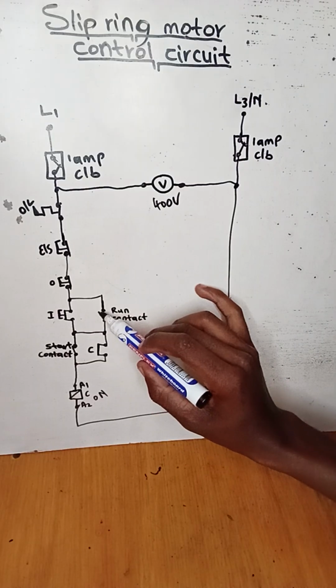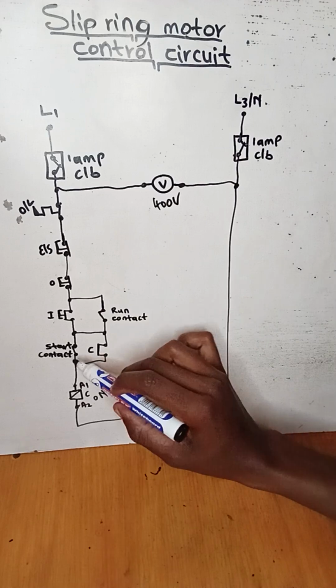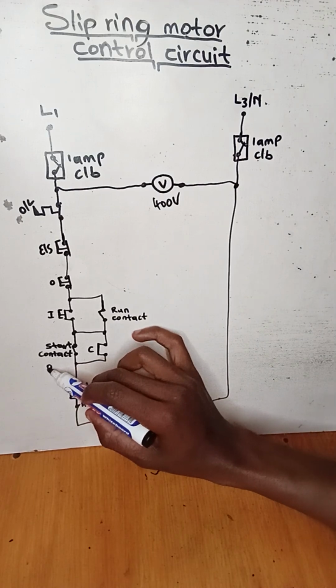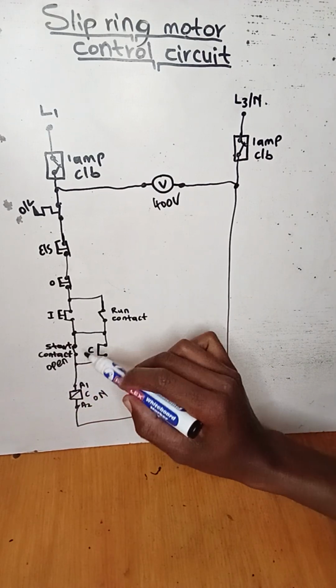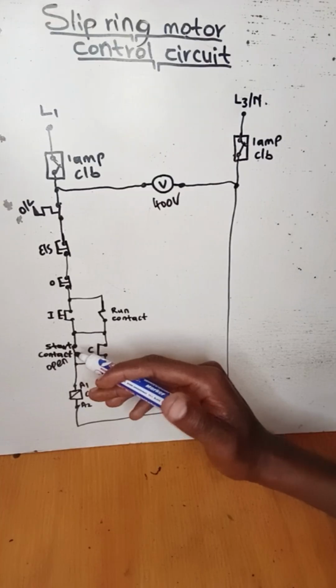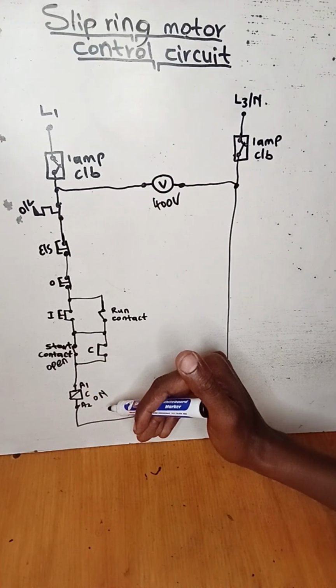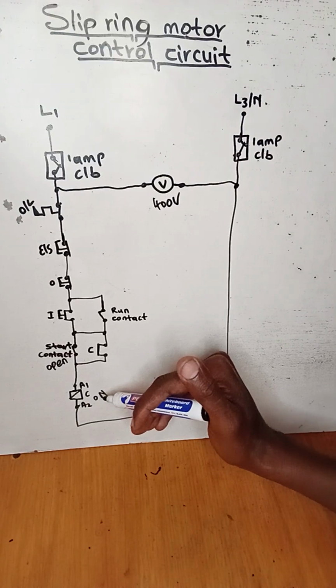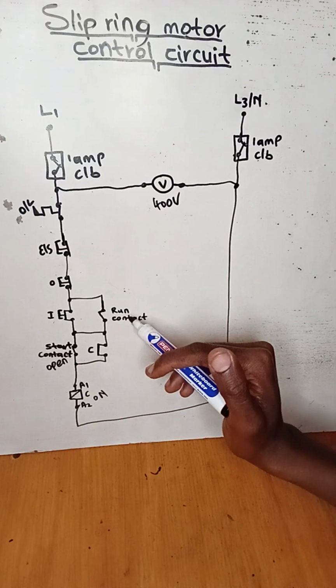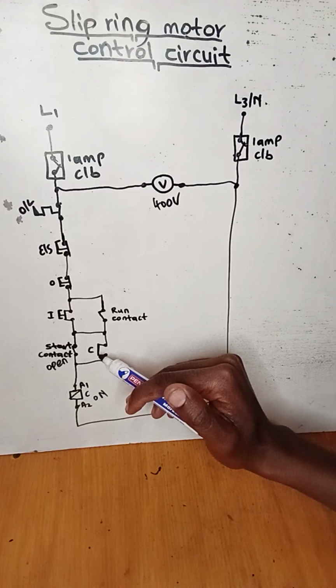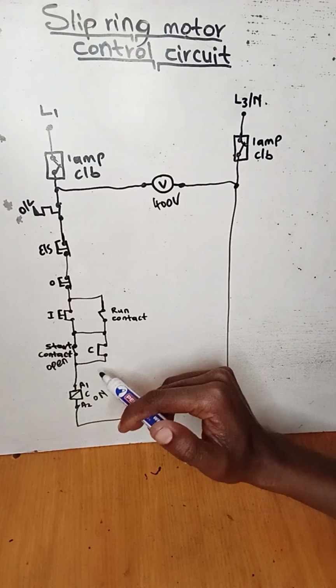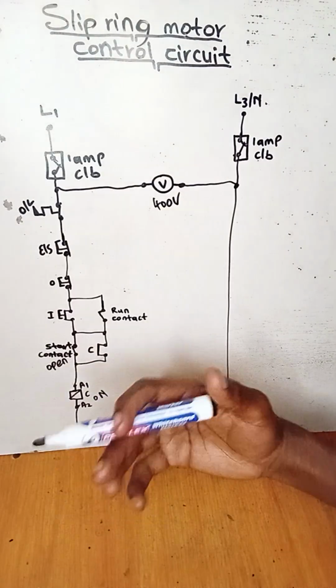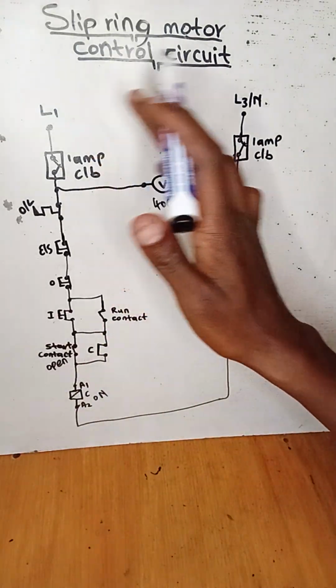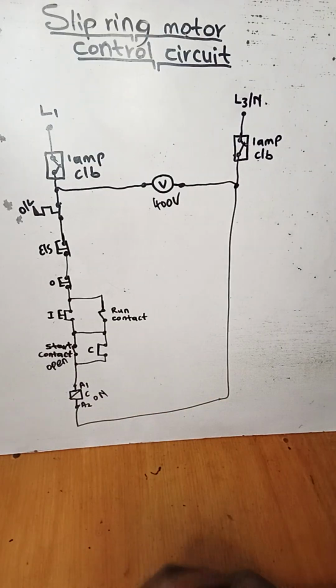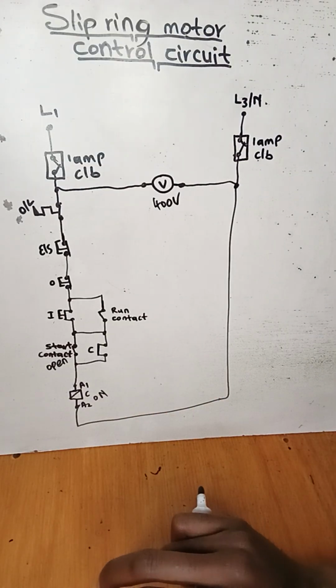the run contact to be closed and the start contact to be open, because the start contact has helped us to start the coil of the contactor, and the run contact and the retainer of the contactor are the ones that will help the coil to keep on running. So that's how the control circuit of the slip ring motor operates. So that is it about it.